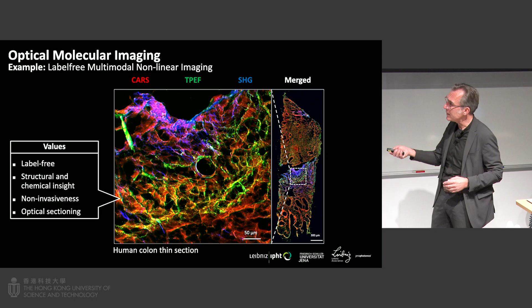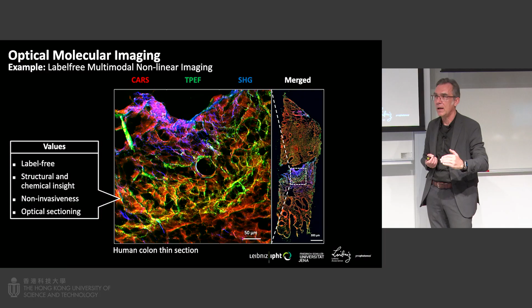You can go, depending on the wavelengths we are using, up to 200 or 300 microns. If we use wavelengths at 1800 nanometers for the excitation, we can go even millimeters into the tissue. And this optical sectioning means, because these signals are just produced within the laser focus, because these are nonlinear processes, you also have direct confocal information. So you get this information just out of a 1 micron thick layer. This means you can really go deep into the tissue, and you don't have information from the upper or the lower layers. And this makes it quite unique.